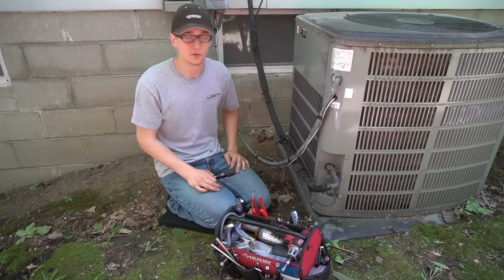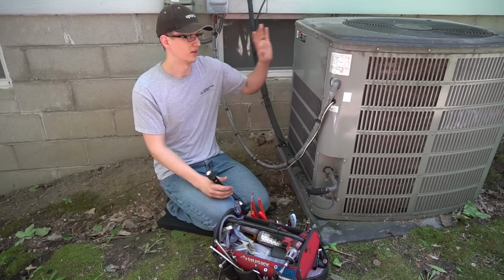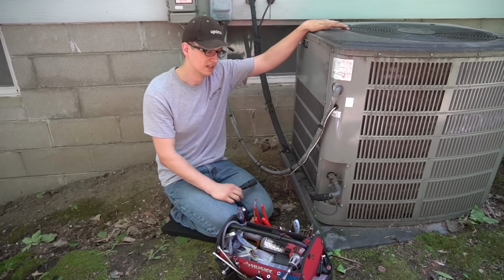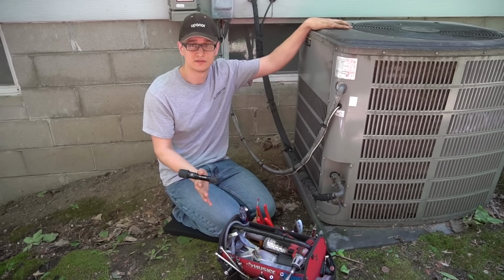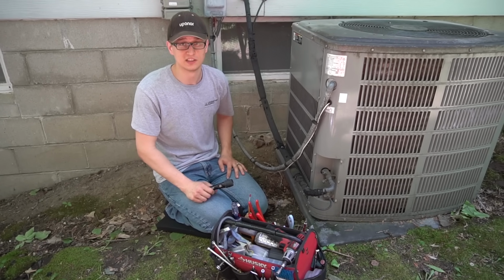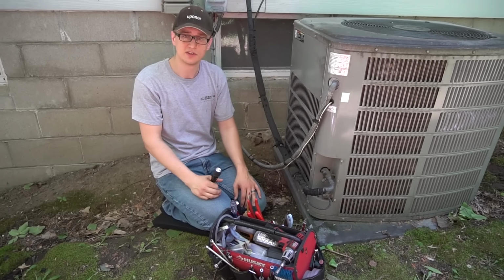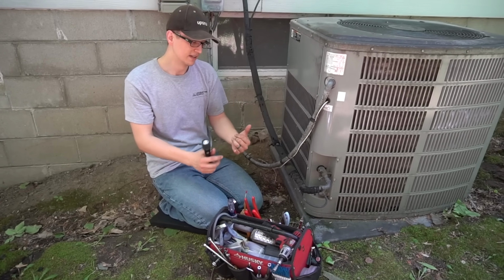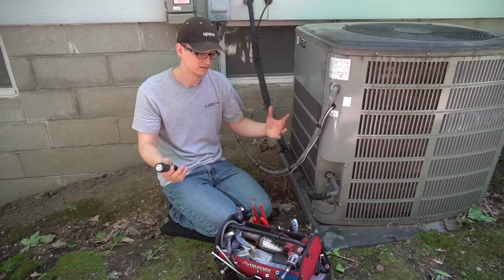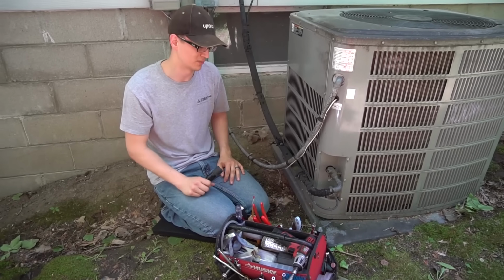If you're having problems with freon, what that will usually look like is everything is going to be running. Your inside and outside units, your compressor you can hear running, your fan's running, the inside fan's running, but it's not cooling the house. Unfortunately, when it comes to freon, you're probably going to have to call a professional, because a jug of R22 refrigerant, for example, is anywhere from $700 to $1,000, and then you need to have a license to buy it, and you have to have special gauges to put it in. And to top it off, you have to know what you're doing. So hopefully that is not your problem, because that's one of the worst problems to have.